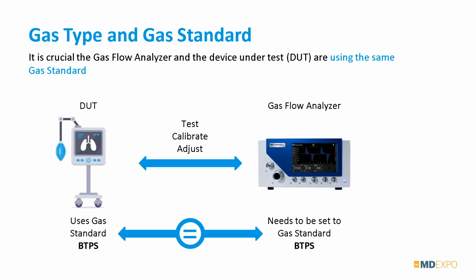And I know this sounds like it makes total sense right now, but I can't tell you how many times people have said, hey, there's something wrong with my analyzer. It's off. It's not reading what my ventilator's telling me. And so I'll say, well, how about you make different settings on your ventilator? Go up to 1,000 milliliters or 800 milliliters, or go down to 200 milliliters, and tell me what the analyzer's reading. Is it reading about 10% high on all of those, or low on all of those? And if so, you probably have a mismatch between your gas standards. It happens all the time.